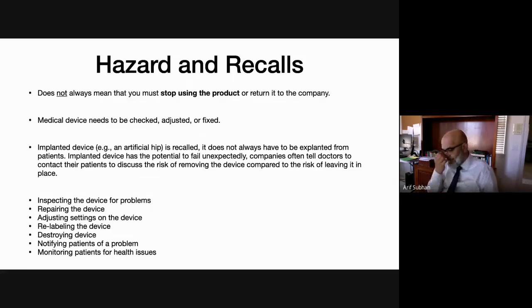And that's another area where it varies based on what type of device it is, what the nature of the recall is, what kind of problems can happen, and what can be done to remove it. Now, that's more for the implantable side of the house that BMETs don't normally deal with. But on the equipment that is in the hospital, it could be as simple as going in and inspecting the device. They tell you to go look at this part, this module, and see if there are any problems, because they noticed that this was a problem in 50 different pieces of equipment in different hospitals. But you may go there and find out that after inspecting that device and checking that particular module or subsystem, it's fine, no problem.